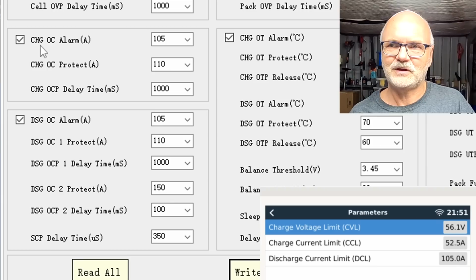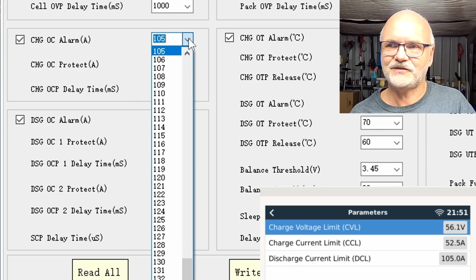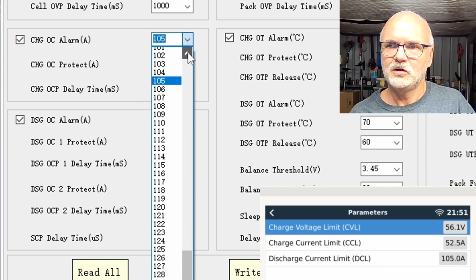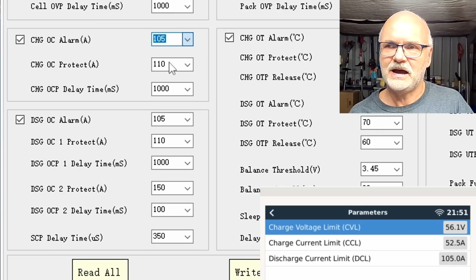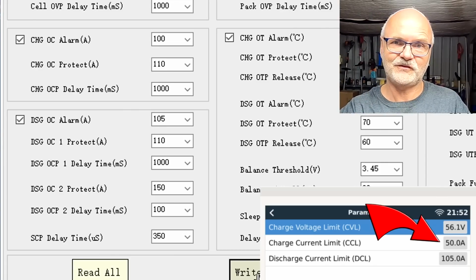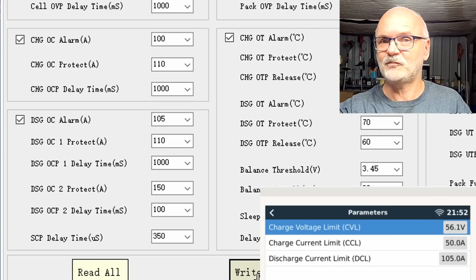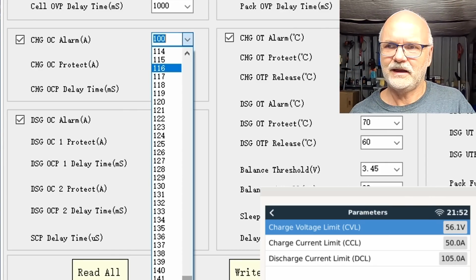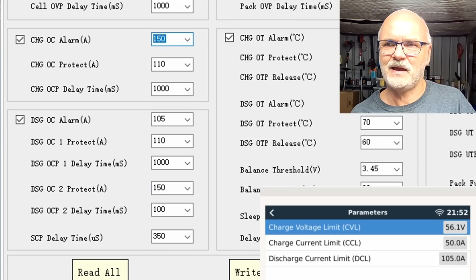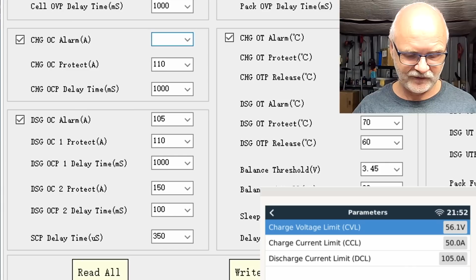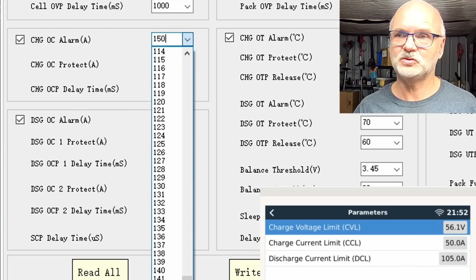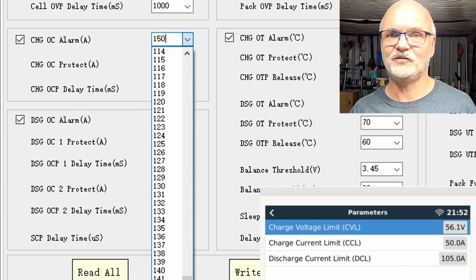The charge current limit is on 52.5, so we don't have any parameters here sitting on 52.5 amps. And we can see the charge overcurrent alarm sits on 105. So let's set this one here to 100 amps and write it back and see if the parameter changes. So the parameter in the Victron system is exactly half of what you have to set in the BMS. And I had a look in this drop-down menu. We can only go to 150 amps maximum as an alarm. So 150 is the maximum, which means 75 amps into this battery.